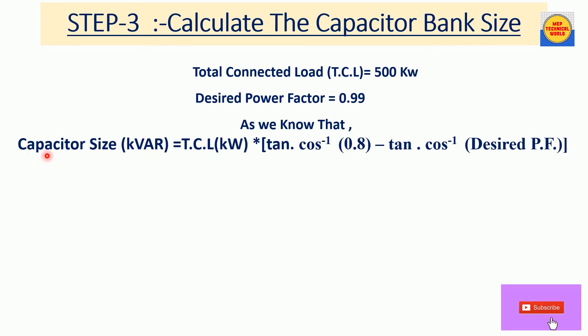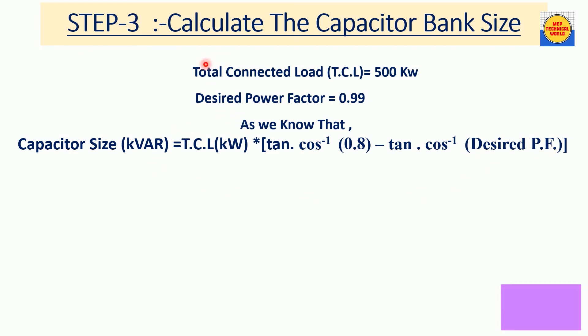The formula for capacitor bank size, rated in kVAR, is: kVAR = total connected load × [tan(cos⁻¹ 0.8) − tan(cos⁻¹ desired power factor)]. Here 0.8 is the reference power factor value we always use.